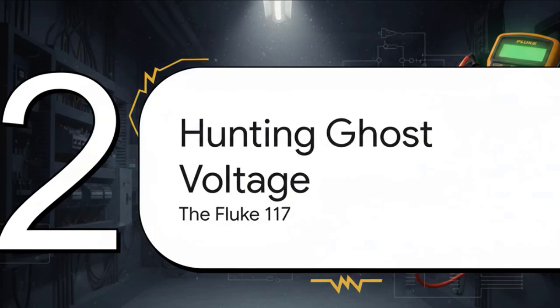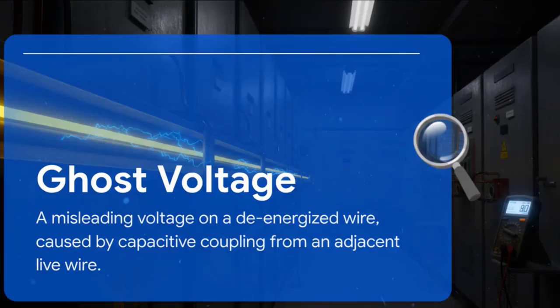So let's leave the industrial plant for a minute and head over to a commercial job site. The dangers here are a little different, but they're just as real. We're talking about hunting down something called ghost voltage, and there's one tool that was born for this fight. So what the heck is ghost voltage? Imagine you've got a dead wire running in a pipe right next to a live one. The energy field from that live wire actually induces a small phantom voltage onto the dead wire. A normal high-impedance meter will see that and show you, say, 80 volts. It tricks you. It makes a safe circuit look hot, and that is a recipe for disaster.